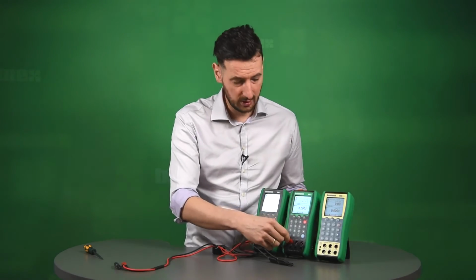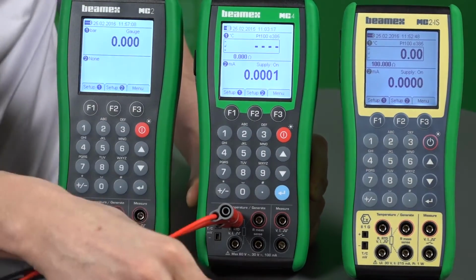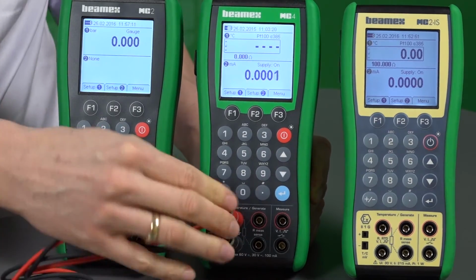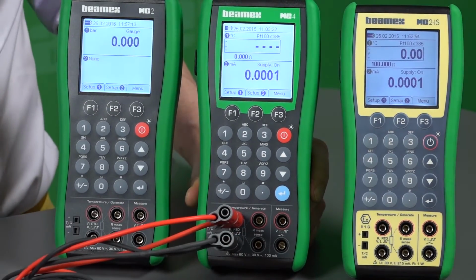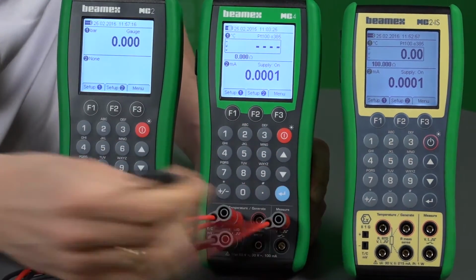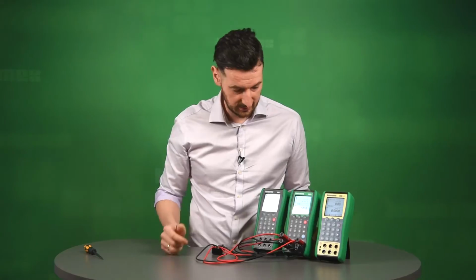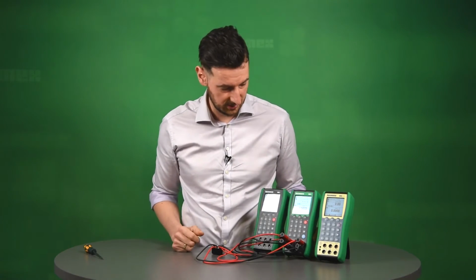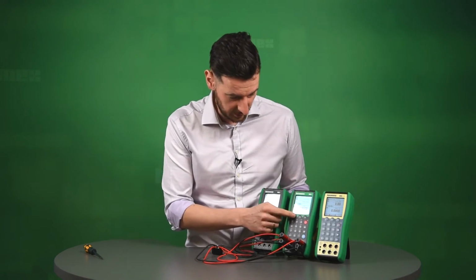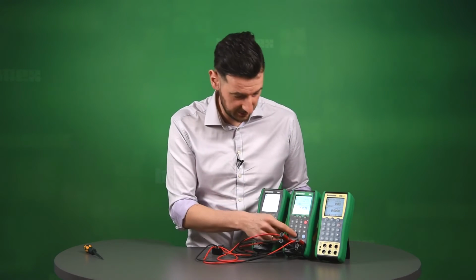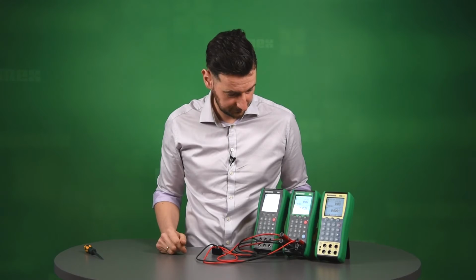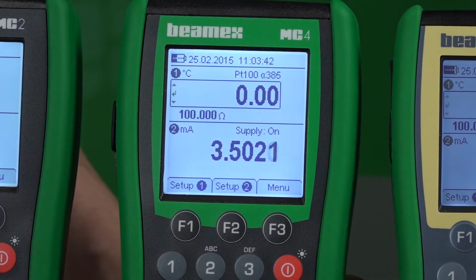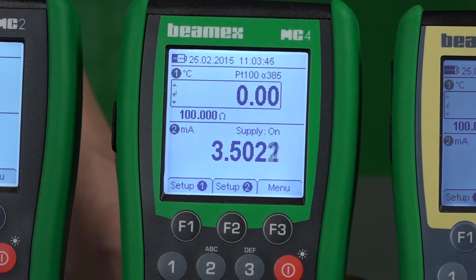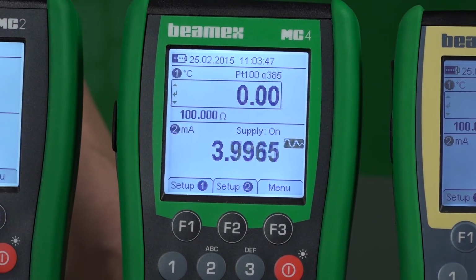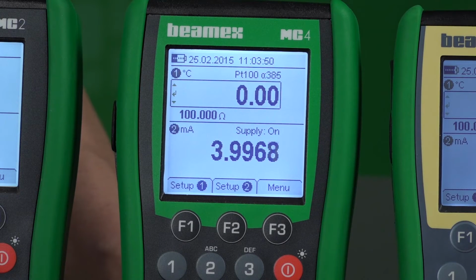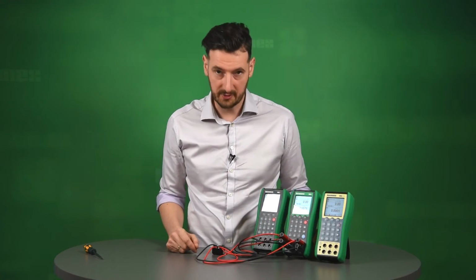As I explained before, I'm going to connect on two sides of the resistor, so black and red test leads going in like this, and then I'm going to connect the milliamps reading to where it should go on the measure side of things. So if I go right now to simulate a value, we should have some feedback milliamps output from the transmitter directly into our unit. Okay, it looks like we've got everything connected right.